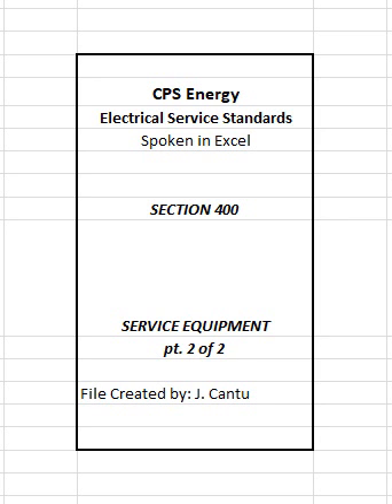411 Raceway seal. Where service raceways enter a building or structure from an underground distribution system and moisture can enter through them to contact live parts, they shall be sealed or plugged at either or both ends. Spare or unused raceways shall also be sealed. Sealants shall be identified for use with the cable insulation, shield, or other components.